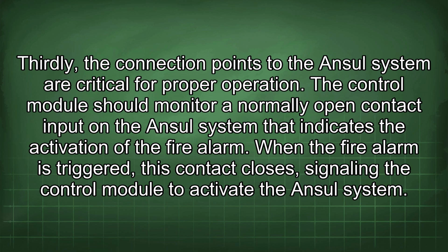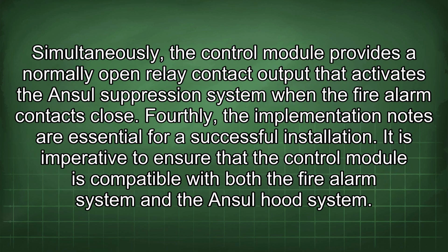The control module should monitor a normally open contact input on the Ansul system that indicates the activation of the fire alarm. When the fire alarm is triggered, this contact closes, signaling the control module to activate the Ansul system. Simultaneously, the control module provides a normally open relay contact output that activates the Ansul suppression system when the fire alarm contacts close. Fourthly, the implementation notes are essential for a successful installation.